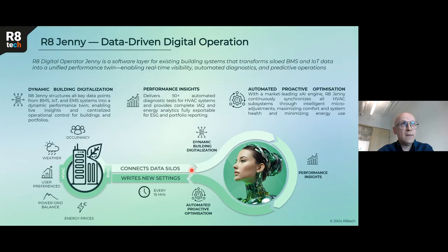And we group all the points to different components. It means one component is one air handling system, the second one is a room, then is a heating circuit and its sub-circuits, and the same for the cooling side as well. And we make the connections between them. So the room is connected with a ventilation system that is serving that room, and also the room is connected to a heating sub-circuit and a cooling sub-circuit.